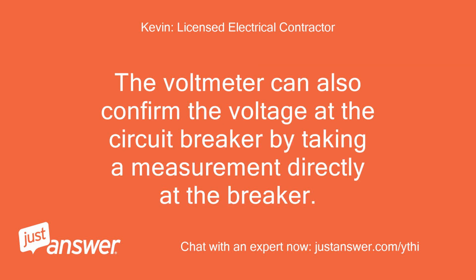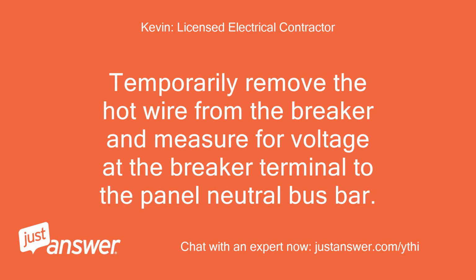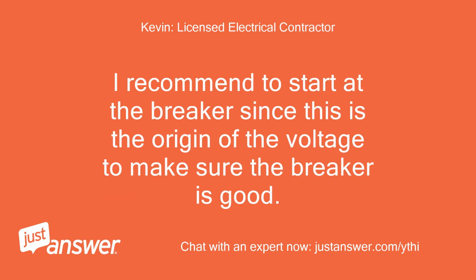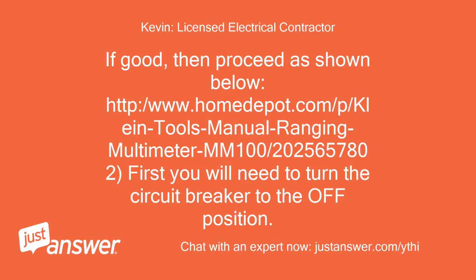The voltmeter can also confirm the voltage at the circuit breaker by taking a measurement directly at the breaker. Temporarily remove the hot wire from the breaker and measure for voltage at the breaker terminal to the panel neutral bus bar. I recommend to start at the breaker since this is the origin of the voltage, to make sure the breaker is good. If good, then proceed as shown below.